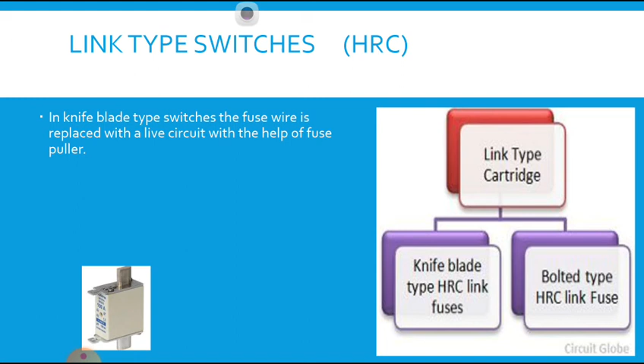Now another type is the bolted type. So what is a bolted type? You can see the figure here. First of all, this is a bolt type. At the starting and at the ending, by using the screw and bolt, we can fix it to the base. That is known as the bolted type. What is the main function? The bolted type HRC fuses have two conducting plates which are bolted to the fuse base. This fuse requires an additional circuit for taking out the switch without getting a shock. Because of the screw bolts, we cannot easily take it out. We require screwdrivers, nose pliers and high insulation materials, so that we can take it from the circuit. This is the one thing you have to remember.